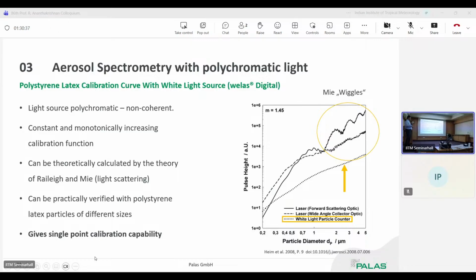And for calibration, you typically need 2 points. The first point in an optical measurement is 0, no particles. So you test the system with the HEPA filter, no particles, okay, 0. And then you can take one of the points of that calibration curve, one size, and test with one size. And that's all you do.